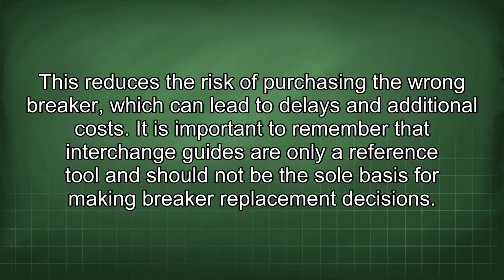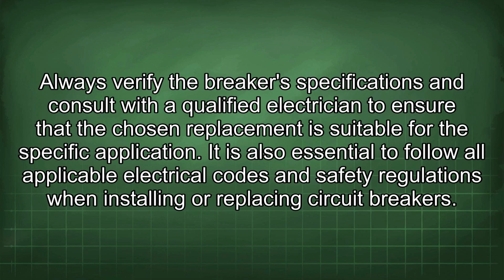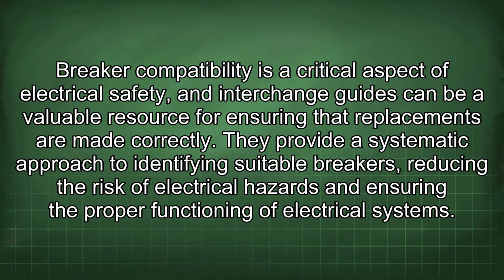It is important to remember that interchange guides are only a reference tool and should not be the sole basis for making breaker replacement decisions. Always verify the breaker's specifications and consult with a qualified electrician to ensure that the chosen replacement is suitable for the specific application. It is also essential to follow all applicable electrical codes and safety regulations when installing or replacing circuit breakers. Breaker compatibility is a critical aspect of electrical safety, and interchange guides can be a valuable resource for ensuring that replacements are made correctly. They provide a systematic approach to identifying suitable breakers, reducing the risk of electrical hazards, and ensuring the proper functioning of electrical systems.